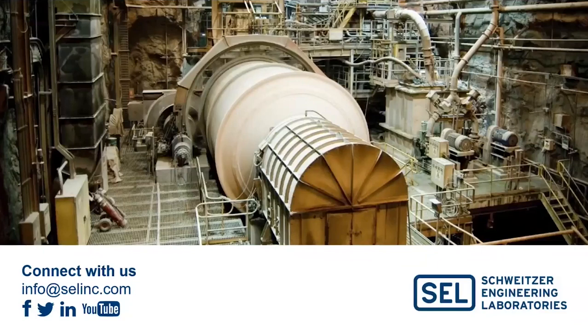All right, thank you. A lot of times switchgear may not have three-phase PTs available. Can we still use single-phase PTs for these transfers? Yes. For the bus, we have a single PT, and for the feeders, that's one of the settings in the relay. You can have any combination of PT, and it doesn't have to be the same on any of the feeders. So you can have any combination of those. Single PT will do too.